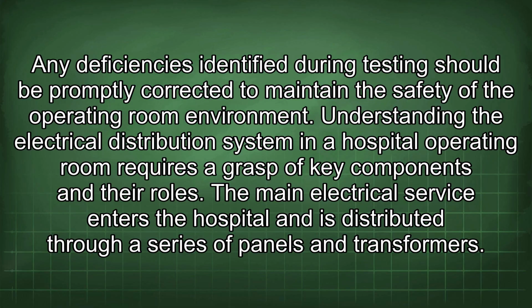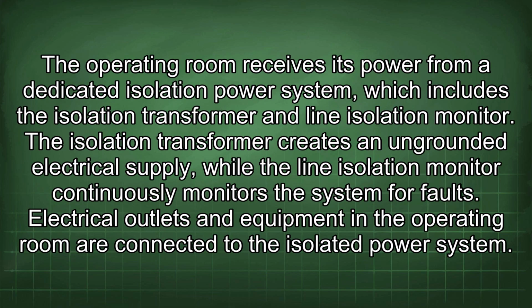Understanding the electrical distribution system in a hospital operating room requires a grasp of key components and their roles. The main electrical service enters the hospital and is distributed through a series of panels and transformers. The operating room receives its power from a dedicated isolation power system, which includes the isolation transformer and line isolation monitor. The isolation transformer creates an ungrounded electrical supply, while the line isolation monitor continuously monitors the system for faults. Electrical outlets and equipment in the operating room are connected to the isolated power system.